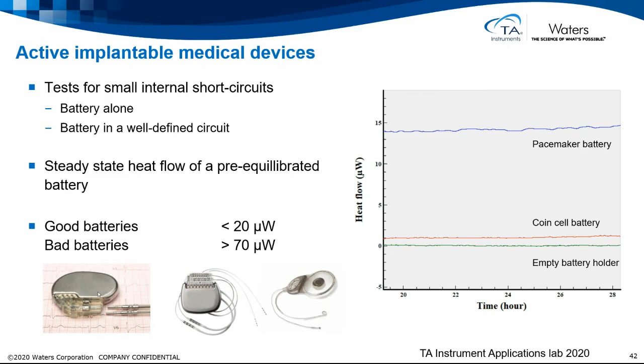On the scale here, we measured for a long period of time, but usually it's just steady state and out of the calorimeter and test the next battery. Good batteries should have below a certain level of heat flow, and bad batteries will have, if there is a short circuit in the battery, it will give up much more heat.